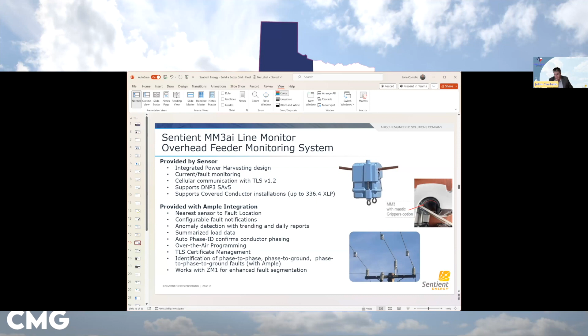One use case for the ZM1 is pairing it with reclosers in the field that aren't communicating—you can see when a recloser actuated and its status at any time. The ZM1s and MM3s all feed into our Ample system, which does the analysis, and in conjunction with circuit models, gets you down to fault location and also feeds your ADMS so you can act on those FLISR schemes.